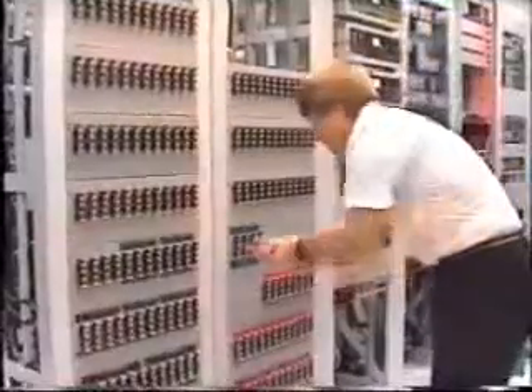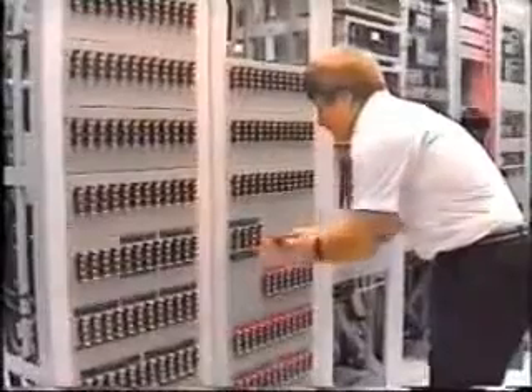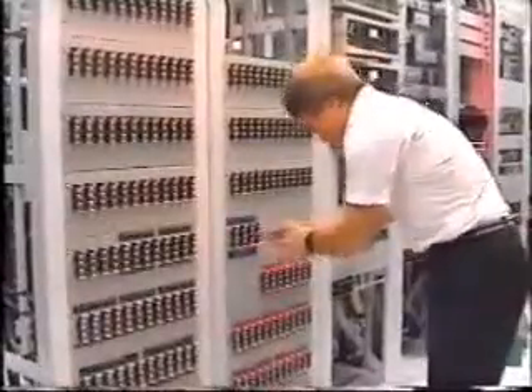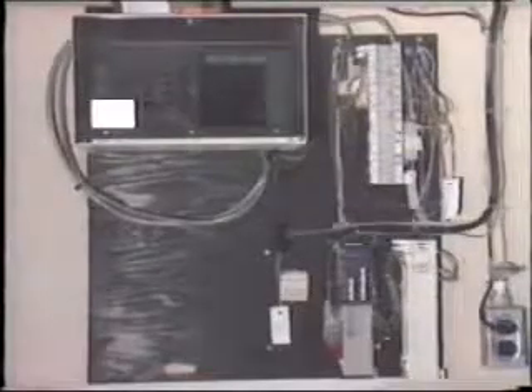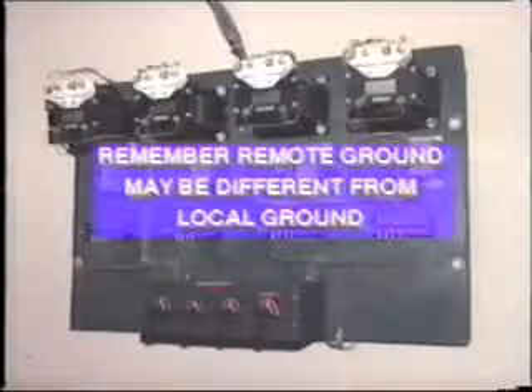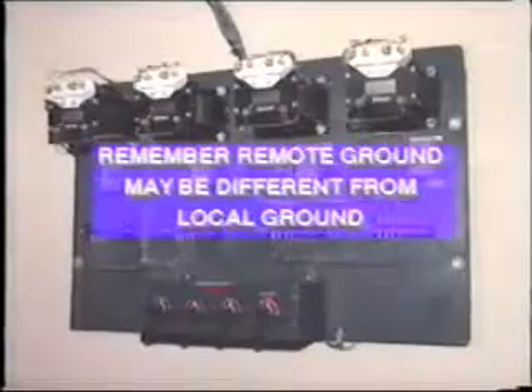You should always take extreme caution when dealing with grounds. Never disconnect a ground connection, as your body may then provide the path for ground currents. All cabinets and metallic structures in a station are normally connected to the station ground mat, so they are all ostensibly at the same ground potential. However, certain incoming cables, such as communications circuits and pilot wire circuits, may be related to ground at a remote location. Remember that this remote ground potential may be different from the local ground potential in the station.